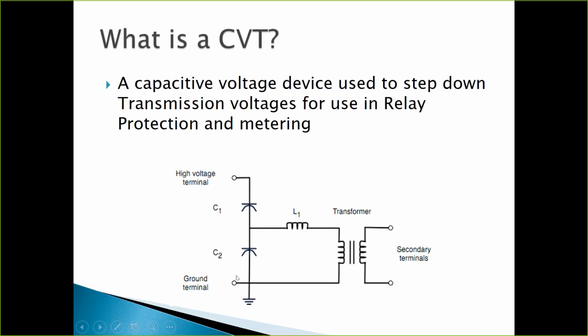It uses a capacitor stack to divide your voltage down from your line to ground voltage down to a usable voltage down here in an inductive pot at the bottom. Typically, at this point, you can have between 5 kV and 11 kV feeding your inductive transformer. Then on your secondary terminal, this is where you have your 120 volts that feed your relays, your meter. And so it gives you an accurate representation of the primary voltage and the quantities in the secondary terminal.